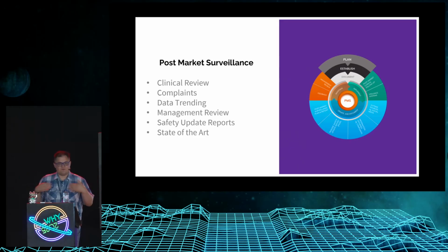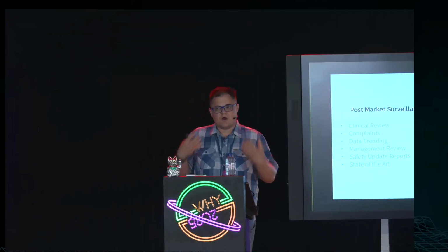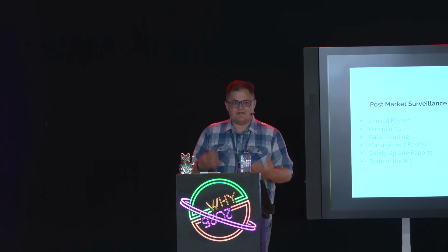Next are complaints. Anytime something goes wrong with a medical procedure, doctors actually have to file, or are supposed to file, a formal complaint and tell the manufacturer what happened. And the manufacturer has to investigate and figure out, like, was this a user error? Was this a design error? Was the error within the rate we expected? Similarly, we have to trend data from the field, both from complaints, from social media posts, from a million different things to go, is our device safe and secure? Are the errors that are happening at the expected rates that we've said are acceptable, or are they exceeding that?